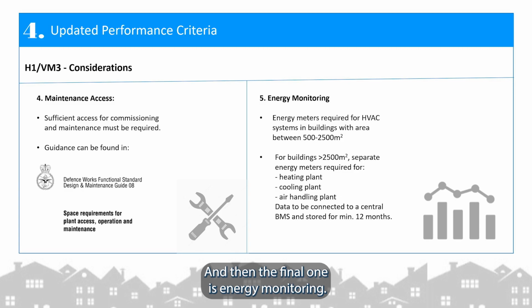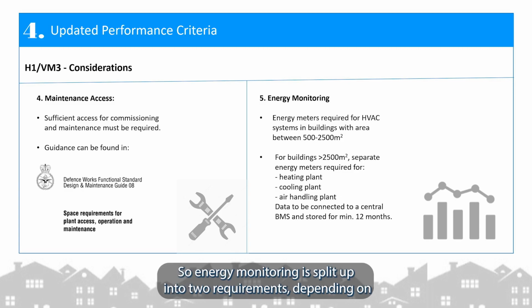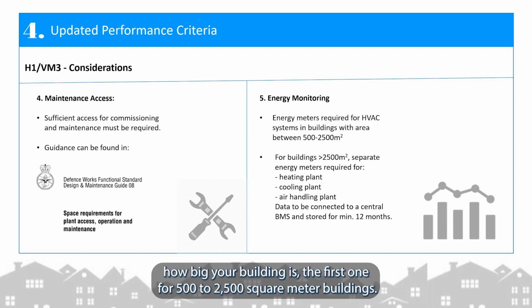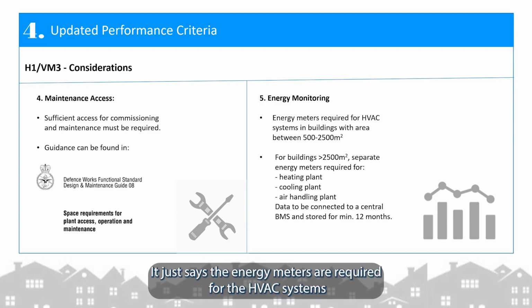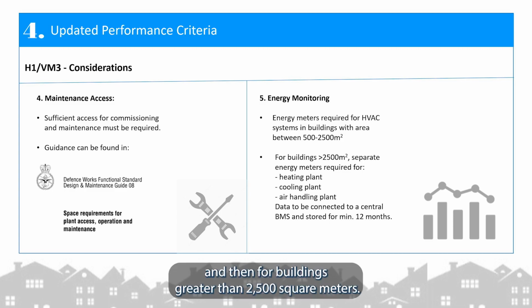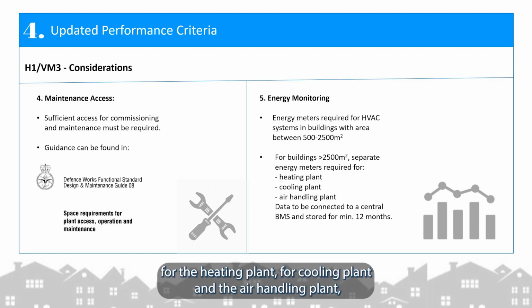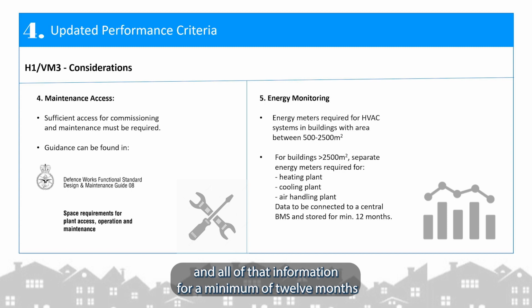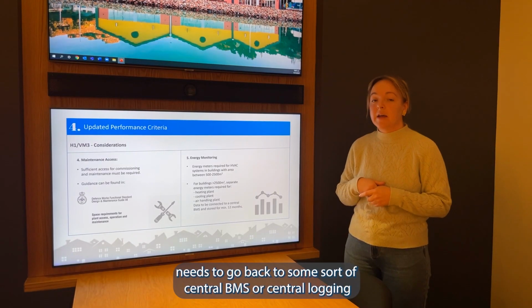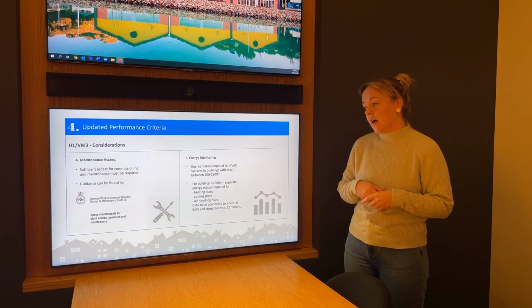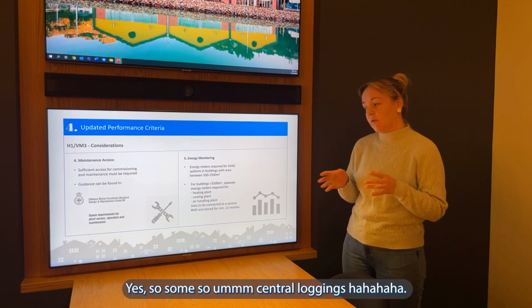And then the final one is energy monitoring. Energy monitoring is split up into two requirements depending on how big your building is. The first one, for 500 to 2500 square metre buildings, just says energy meters are required for the HVAC systems. And then for buildings greater than 2500 square metres, you need separate energy meters for the heating plant, the cooling plant and the air handling plant. And all of that information for a minimum of 12 months needs to go back to some sort of central BMS or central logging.